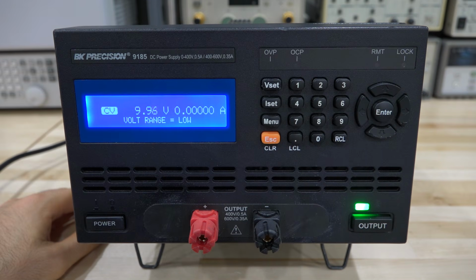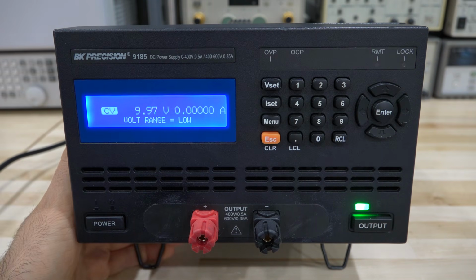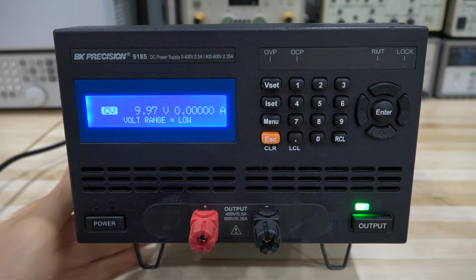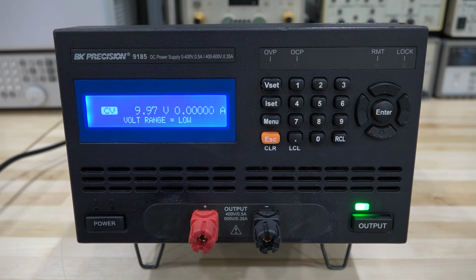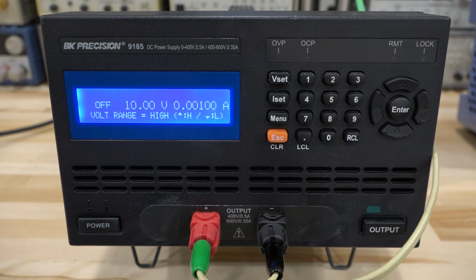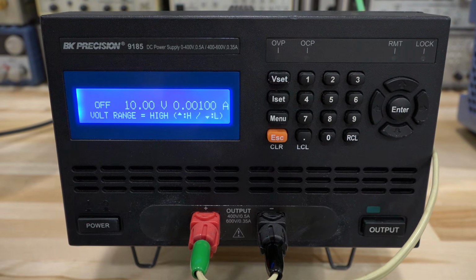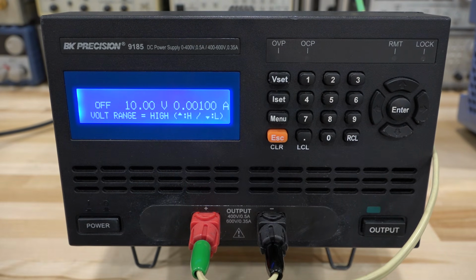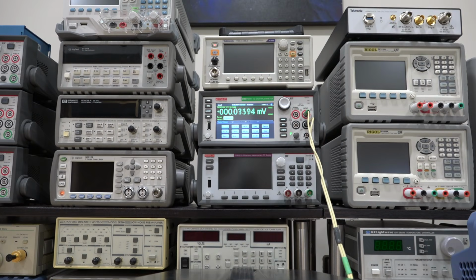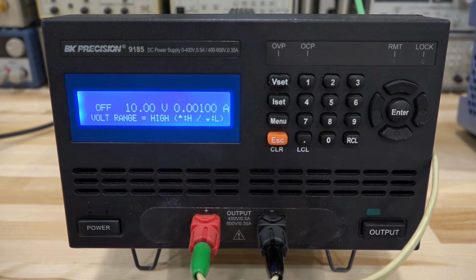So maybe what we should do is connect it to a 7.5 digit meter, like the Keithley one that I have, and run through the calibration cycle and see how well it behaves after the calibration. So let's take a look at a couple of the measurements from this instrument. I have it connected to my Keithley DMM7510, and as you can see, under a 0 volt condition we're reading basically 0 volts. There's a tiny offset, but it's really nothing. Remember, the scale there is in millivolts. So we can go ahead and enable the 10 volts and see what we read.